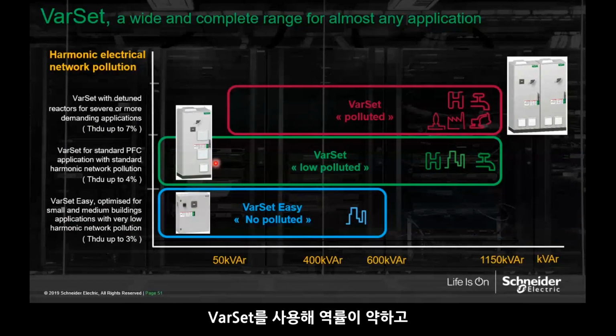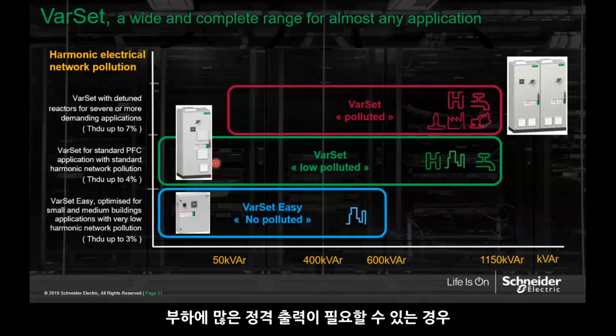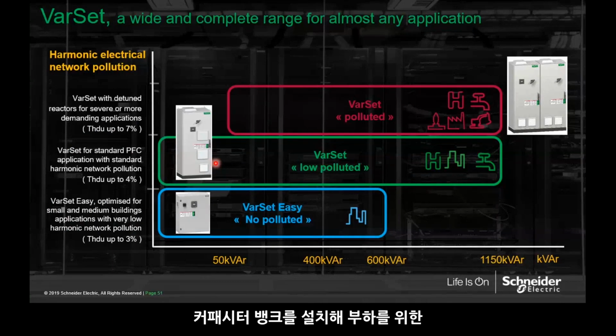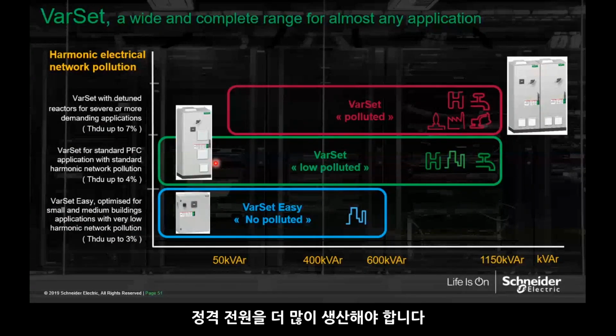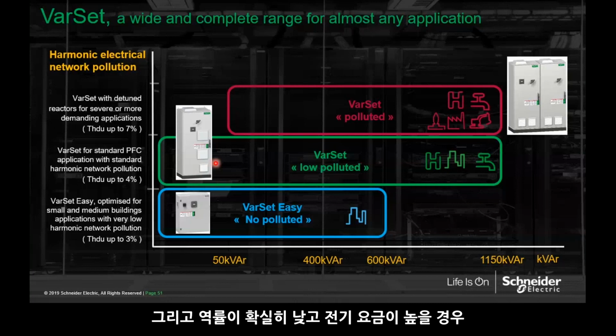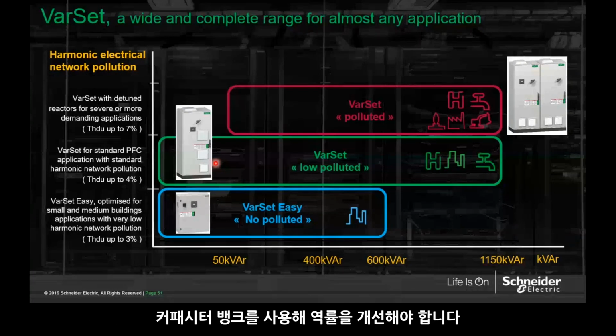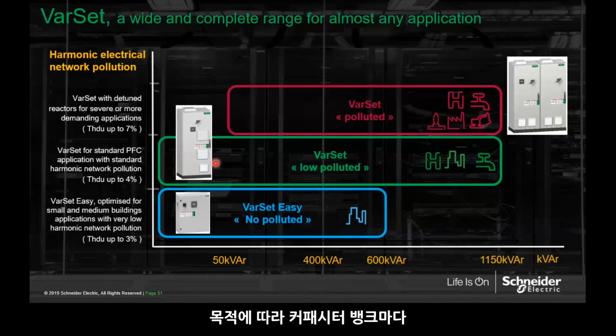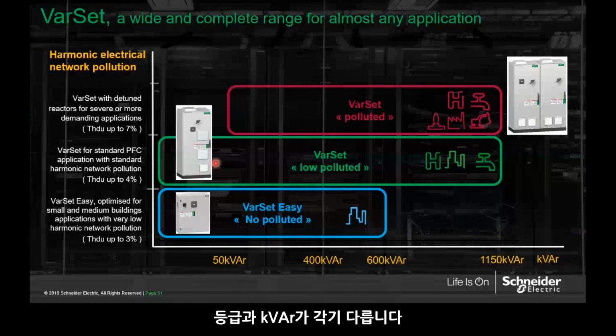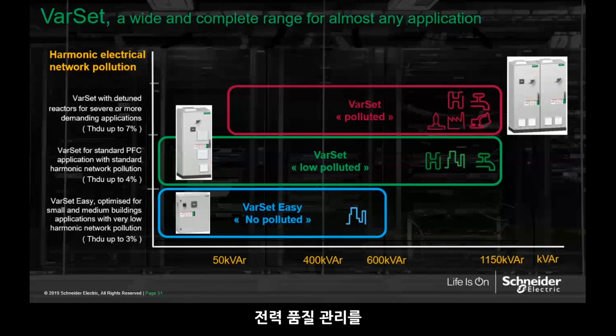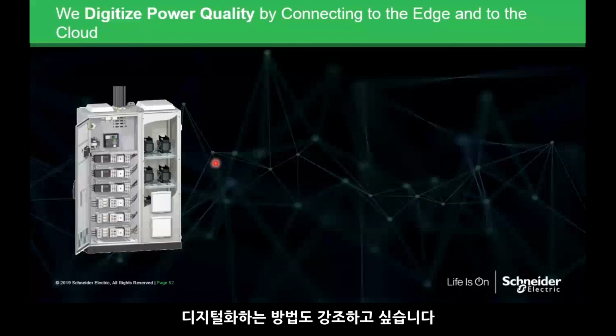We use this VARSET if you have poor power factor at your load, or maybe your load requires a lot of reactive power, then you need to put in a capacitor bank to produce more reactive power for your loads. And if your power factor is below a certain level and you keep getting penalties in your utility bills, then that is where you need a capacitor bank to improve the power factor. We have different ratings of kVAR in a capacitor bank for different purposes. One of the things I wanted to highlight is how we digitize the power quality.